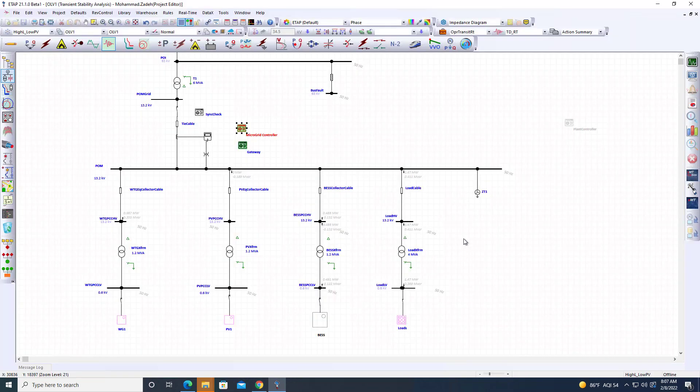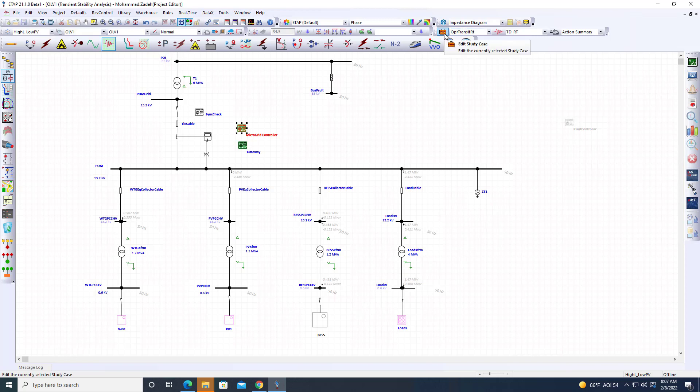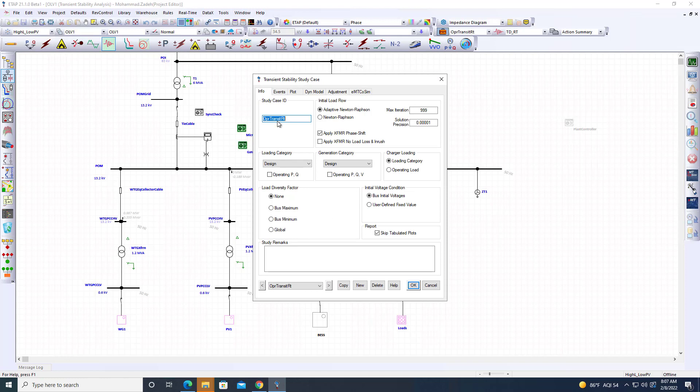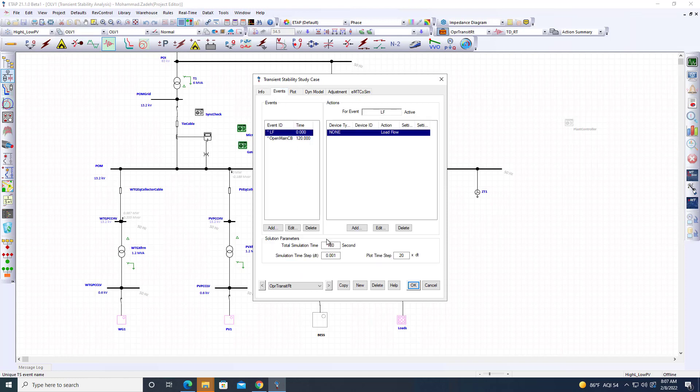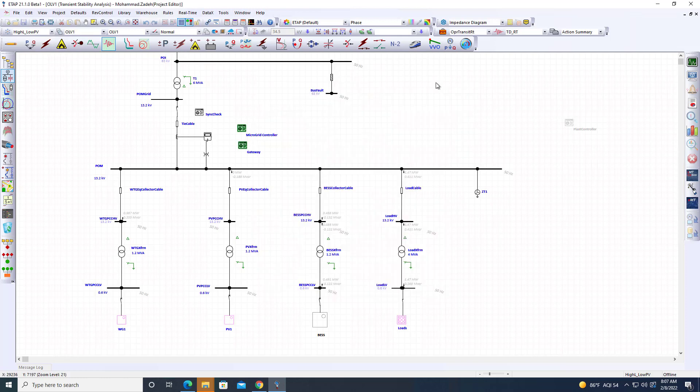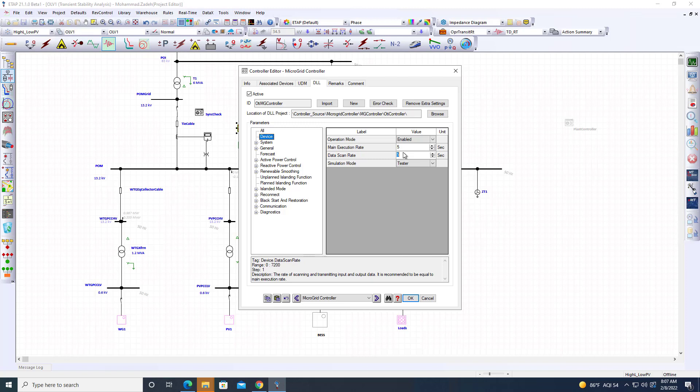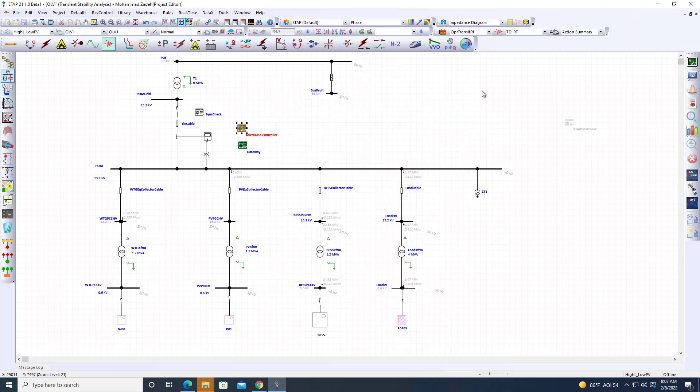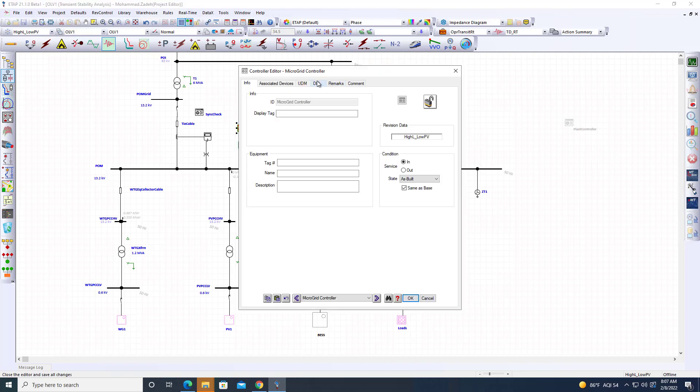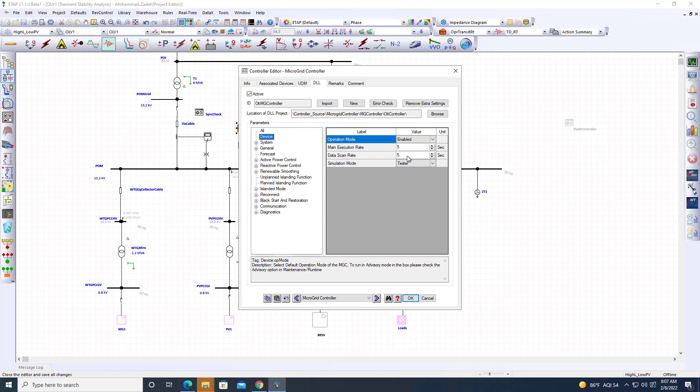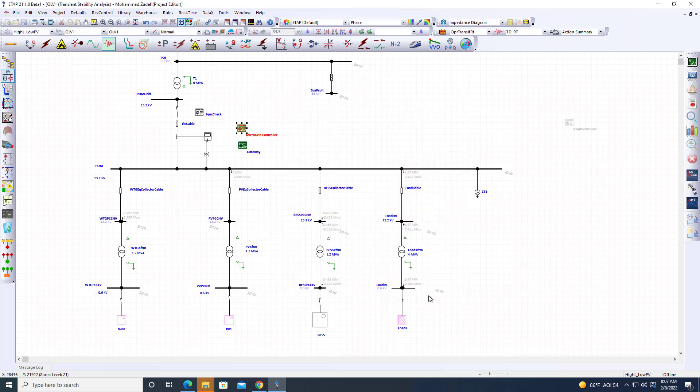Now this system was faster than real-time. If you run this system, it's going to run less than 180 seconds. This means that for this size of the system, a little bit even larger, we can always go real-time. Keep in mind, we are running every one millisecond here in the transient stability, but the data gets exchanged over DNP3 with the resolutions of the microgrid execution rate every five seconds. So data goes every five seconds to DNP3. We can control that. We can go a little bit even faster, every one second to the DNP3, even though microgrid controller runs every five seconds.